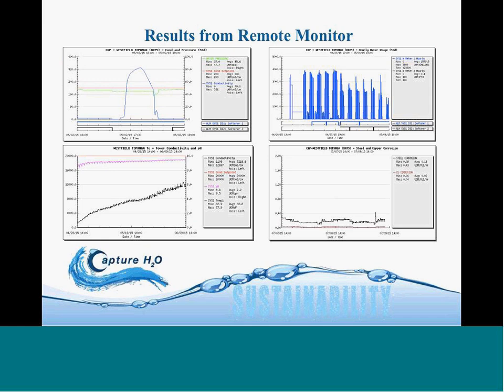The graph to the upper right shows the water usage. You can see that over this period of time the water usage dropped, mainly because we created the environment where we're naturally getting water treatment by not blowing down the water. The graph on the lower left shows the cooling tower conductivity and pH rising because you're not blowing down. And the bottom right graph shows the corrosion rates of the steel and copper.